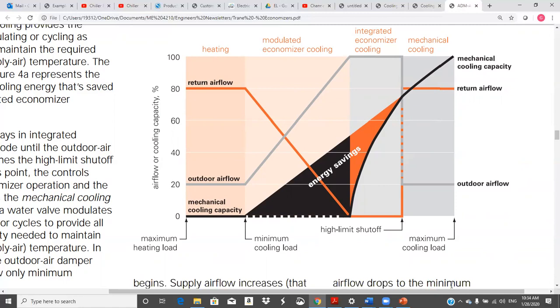Well, this continues, and all of a sudden we get to the point where, up here, 100% outside air, we have no return air. We're just making the load. We're still on no mechanical cooling. Life is great, right? Okay. Then what happens? Well, it got 2 degrees hotter. Oh man, we can't cool them anymore. So what do we do?